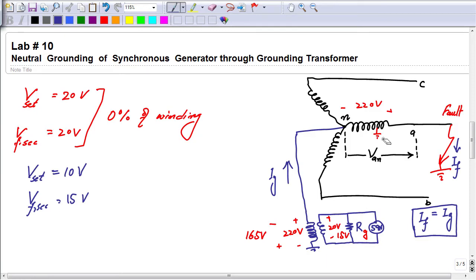Now if the fault moves to the midpoint here, then the voltage from this terminal up to the fault point will be 110 volt because it is exactly the midpoint. Against this 110 volt, the secondary voltage will be 10 volt, which is exactly equal to the pickup setting.